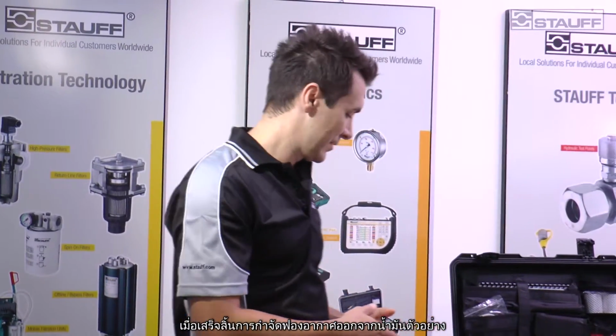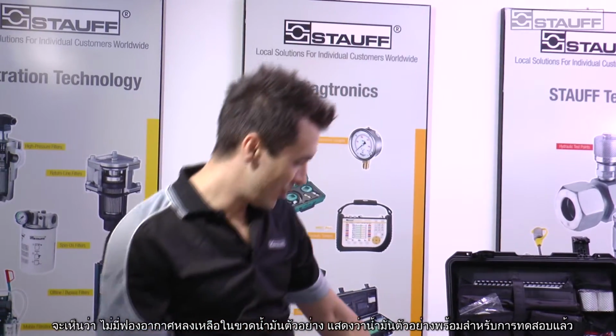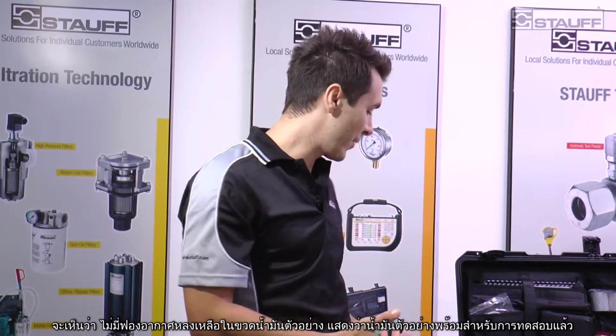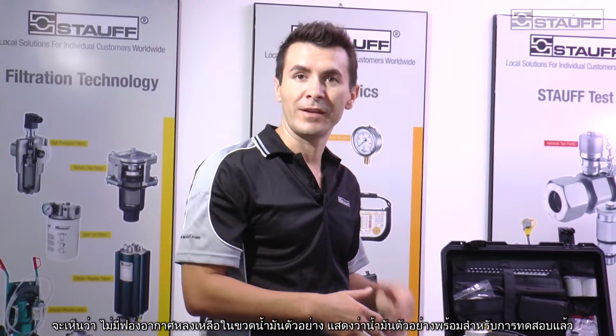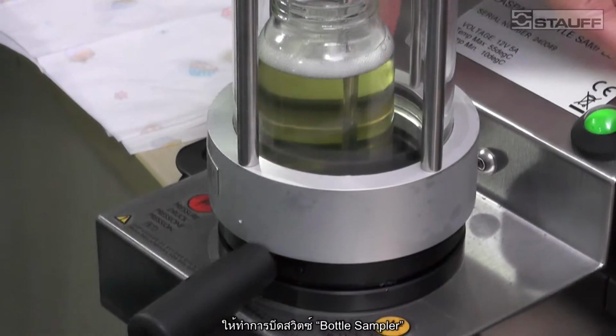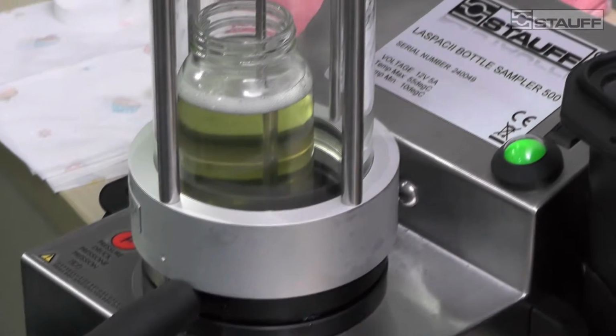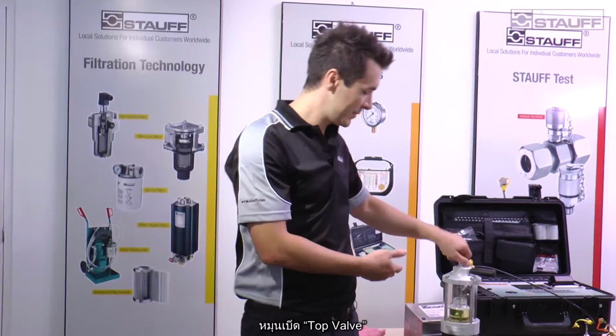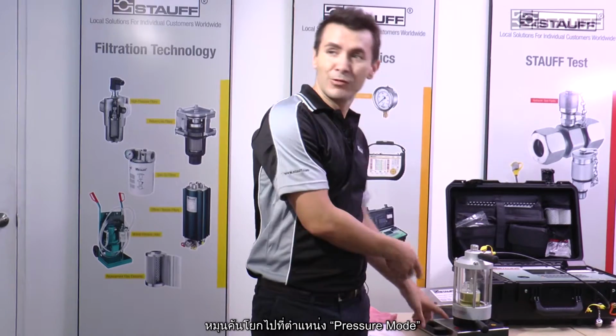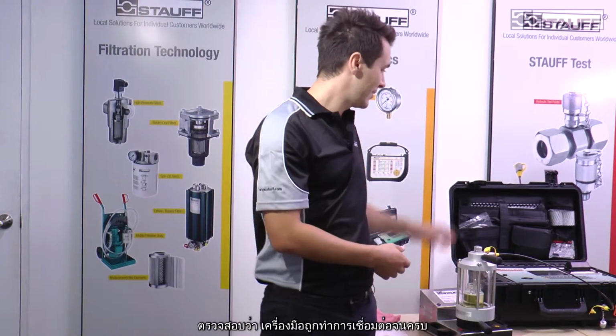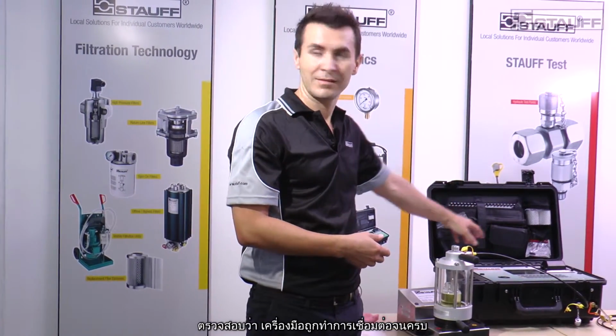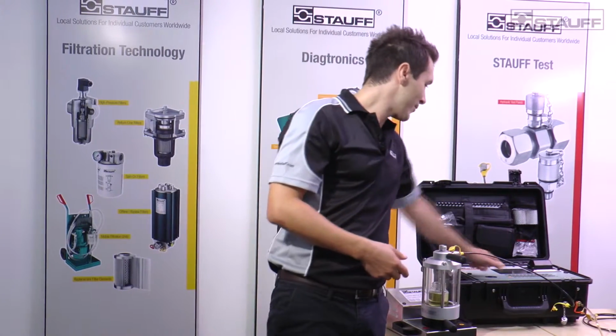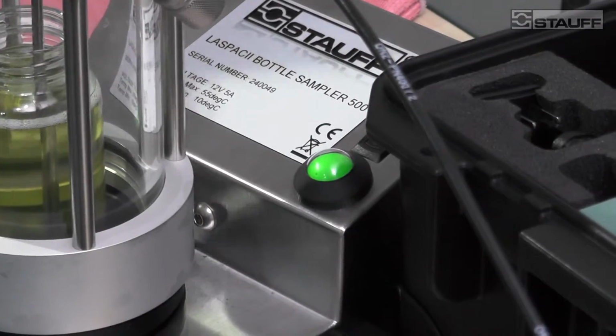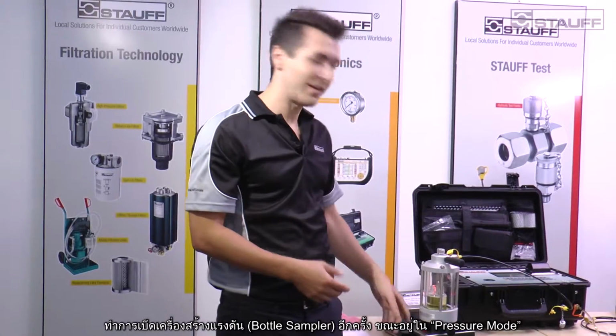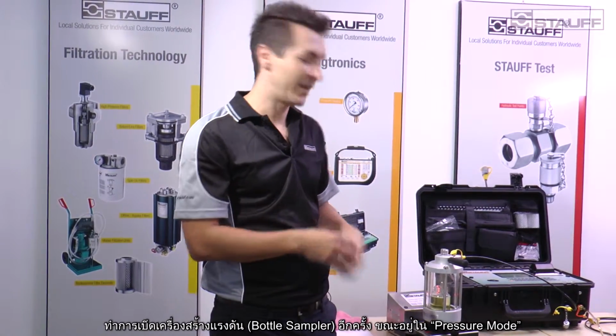Once we finish removing all the air bubbles, so there's no more bubbles down the bottom, so now we are ready to turn it off and then commence the test. So we turn the bottle sampler off, open up the top valve, change the handle to pressure mode. When the machine's already set, so make sure the machine's turned on, and then start the bottle sampler in the pressure mode.